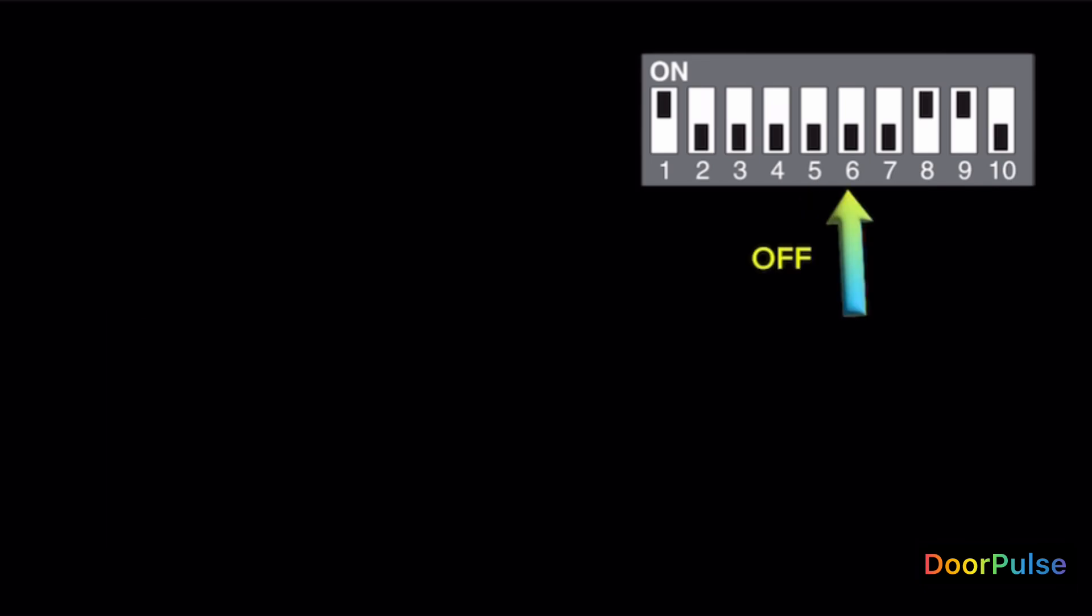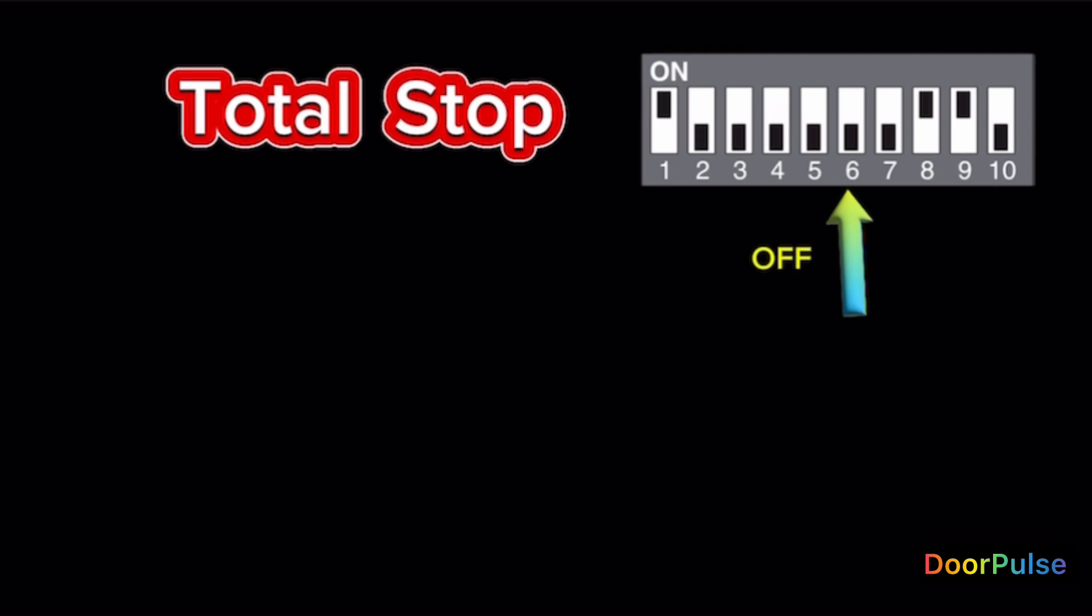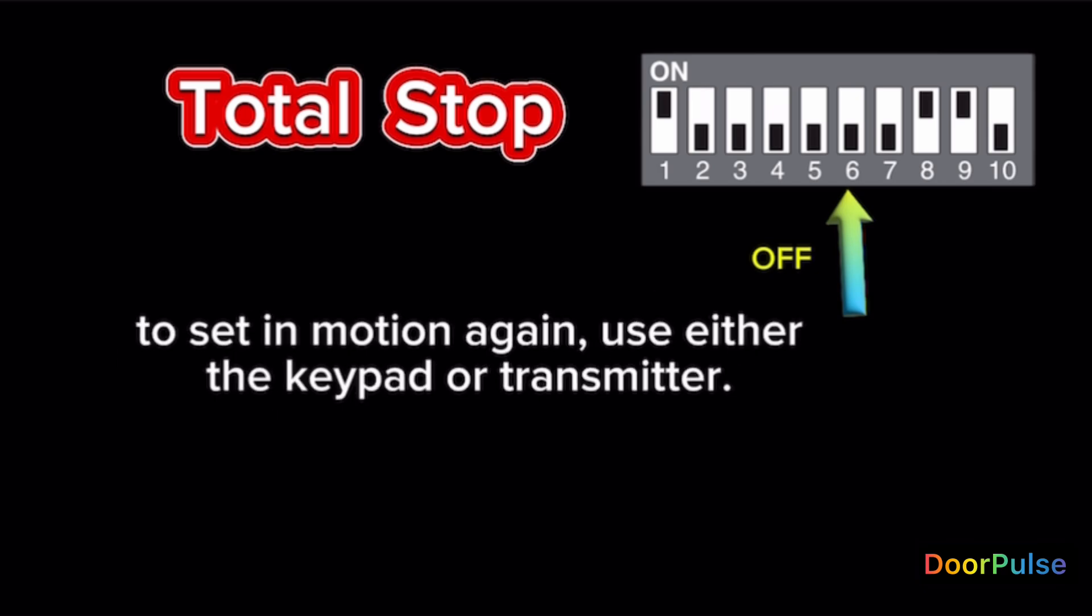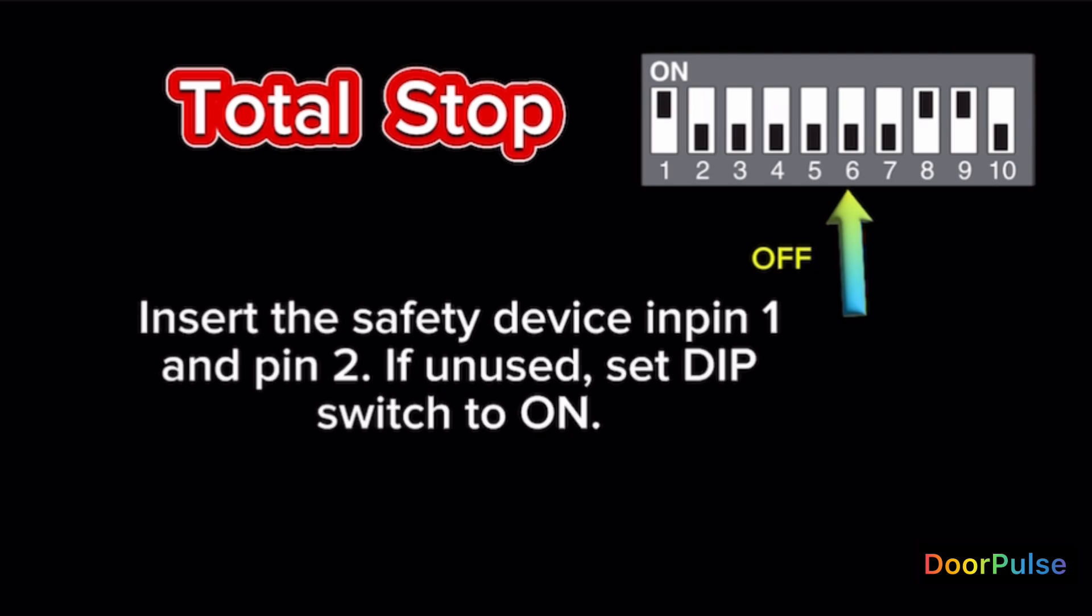Switch 6 OFF. Total stop. This function stops the boom and consequently excludes any automatic closing cycle. To set in motion again, use either the keypad or transmitter. Insert the safety device in pin 1 and pin 2. If unused, set DIP switch to ON.